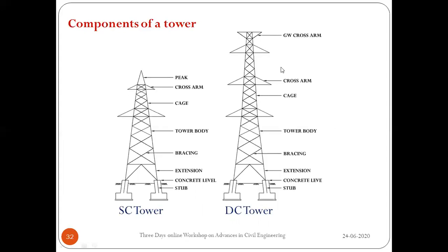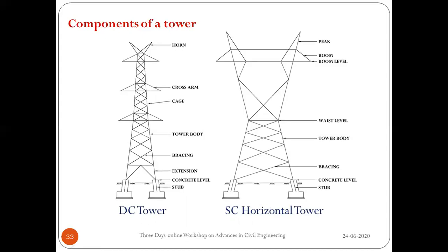Foundation type varies depending on soil type. The double circuit vertical tower has a ground wire cross arm instead of a peak, or alternatively horn arrangements. The right side image shows a single circuit horizontal tower with peaks and a boom — a lattice-type steel beam arrangement from which insulators hang and conductors are supported. In vertical towers, the portion below the bottom cross arm is called the waist level; in horizontal towers, the narrow portion is also called the waist.